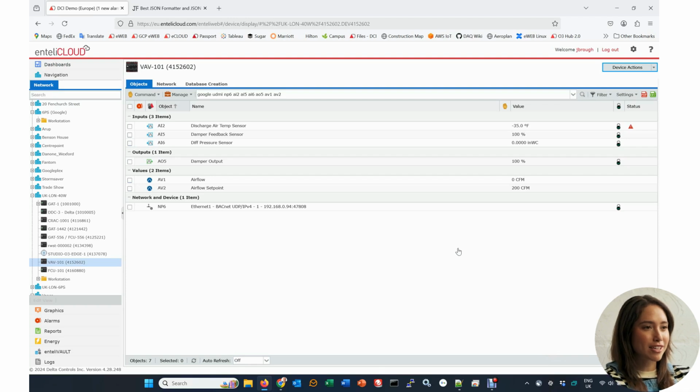This is a huge advantage over other methods, which rely on the device being configured somehow so it knows what data to publish. The key advantage is that the device is managed from the cloud, reducing the number of visits to site to add or remove a point from the point set that is being published, or change the interval, or whatever. Other IoT layers usually have another independent data layer, which just adds cost and complexity to a project and locks the client to that particular MSI because the MQTT payloads are bespoke and only they can change them. UDMI schema has been called the open protocol for smart buildings, and that is a very true statement.